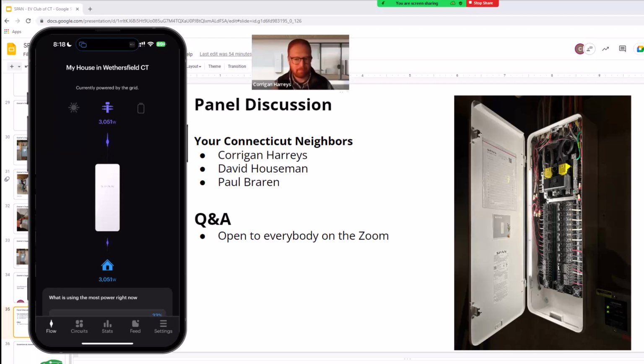There's a few different ways around it with different budgets. If budget's not a problem, you can use two SPAN panels in parallel, one as your main panel and a second fed off a branch breaker or using the feed-through lugs. With two SPAN panels, you'll get 64 data points, so it's expensive, but you get the most data and control.